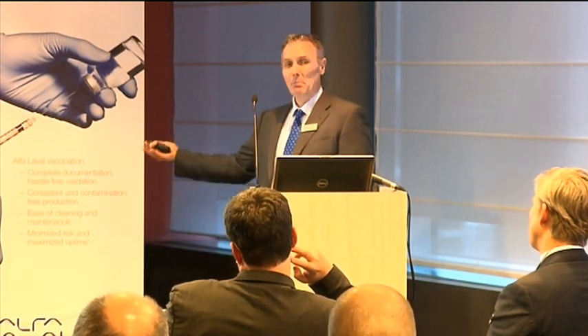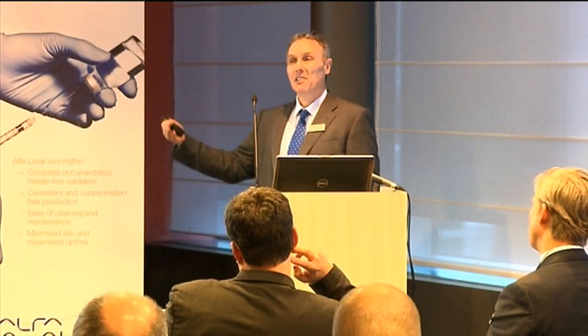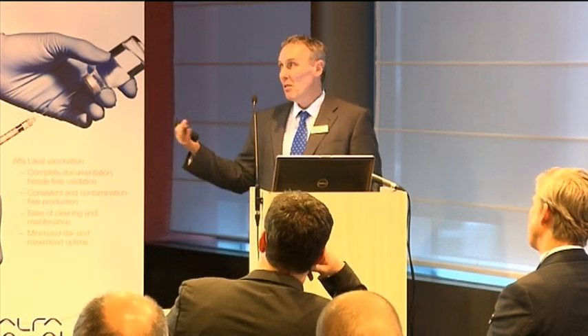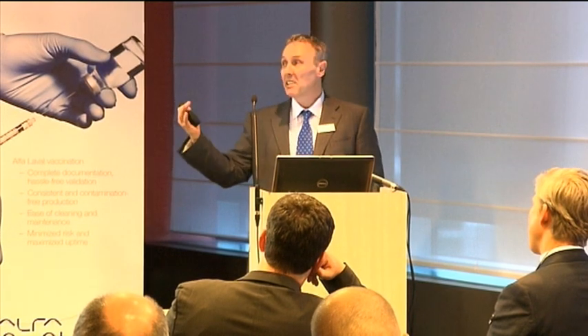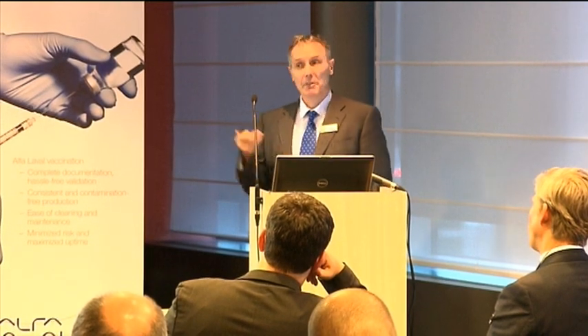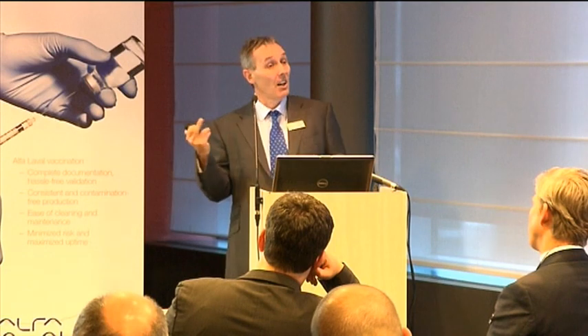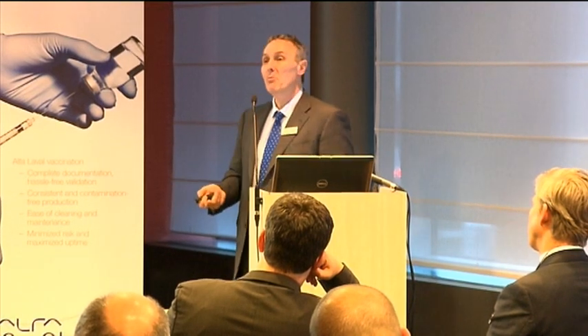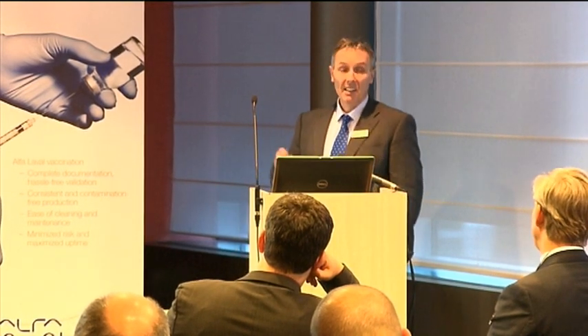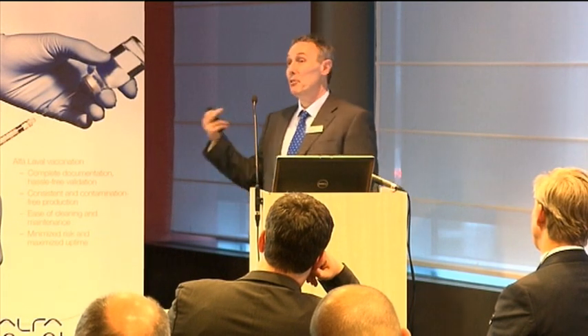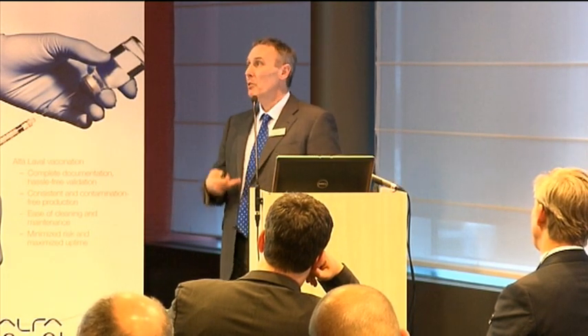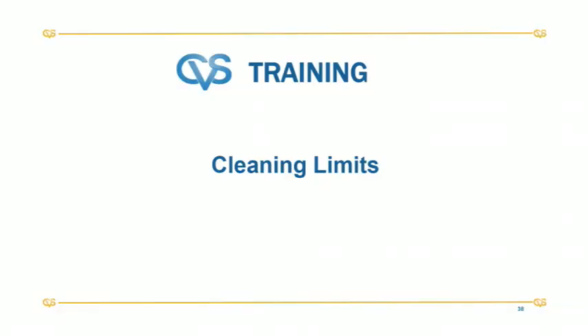Then the key is buy the right parts, have the right system in for detecting they're working, back it up with proper maintenance and inspection as well. If you're running static spray devices, recognise the risks associated with them. The drawback is it's going to take you longer to clean. You can use more energy, more liquid, have bigger effluent costs. But you've got to inspect them regularly.